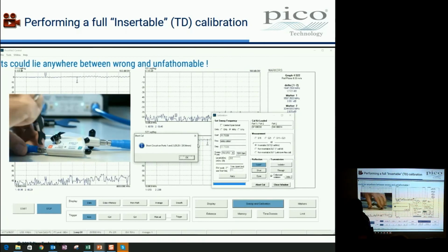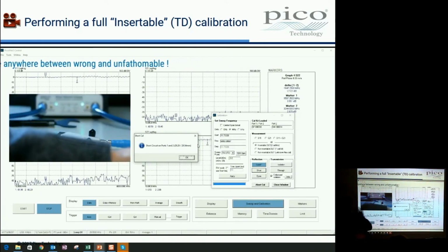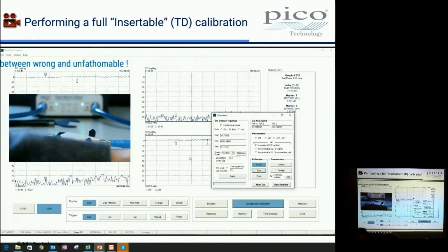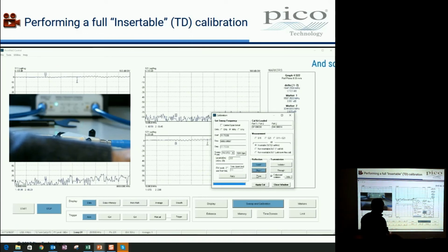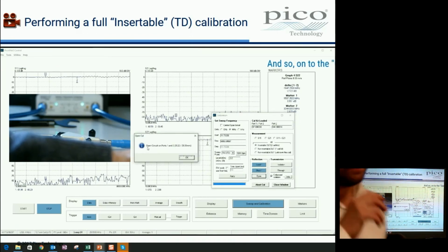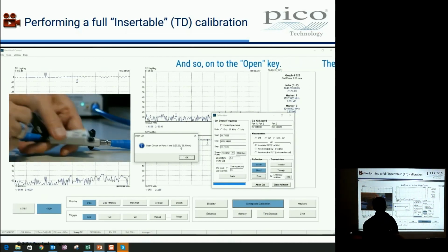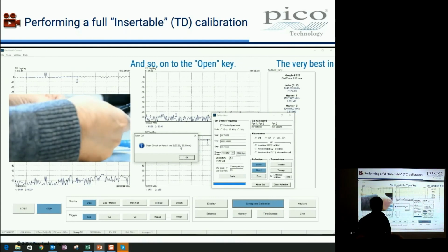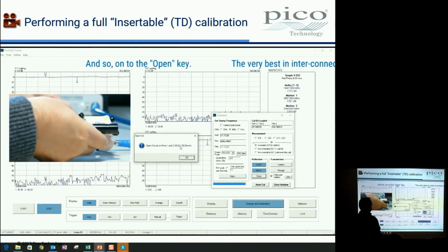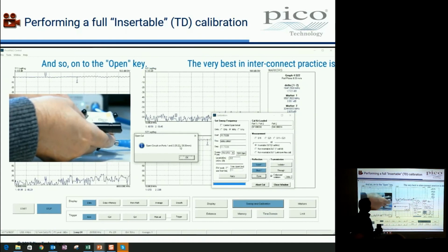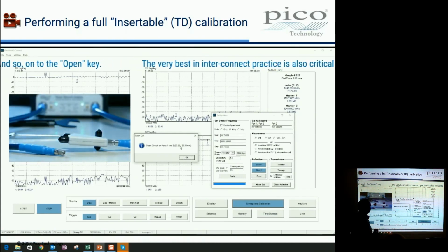And the trouble with getting it wrong is the data that you see on the screen will just send you into a complete spin. You won't know what the data looks like. It's completely unfathomable nonsense on occasion. So you really can be totally misled by making a mistake. So check carefully. Not the process to do in a hurry, which is why I said try to avoid doing calibrations first thing when you need to get the customer settled and you need to tell them all about the product. You don't want to be talking when you're doing this, not too much anyway.